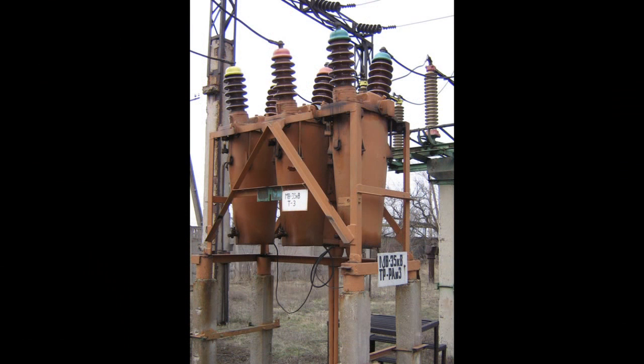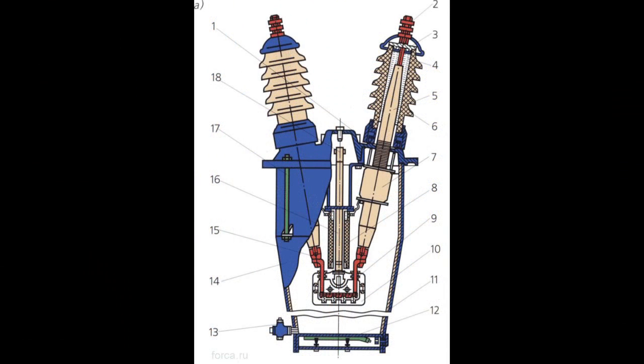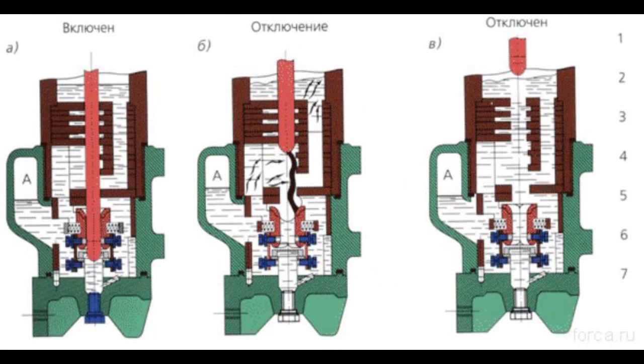When the switch is triggered, the contacts of the arc suppression chambers are broken first. At this point, electrical arc appears. Under the influence of the high temperature of the arc, the oil quickly evaporates.